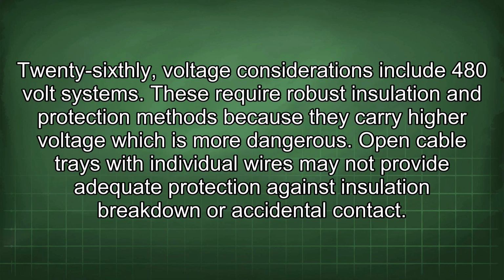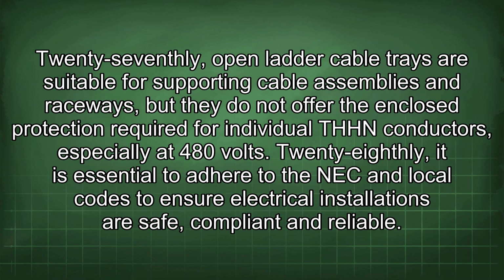26thly, voltage considerations include 480 volt systems. These require robust insulation and protection methods because they carry higher voltage, which is more dangerous. Open cable trays with individual wires may not provide adequate protection against insulation breakdown or accidental contact. 27thly, open ladder cable trays are suitable for supporting cable assemblies and raceways, but they do not offer the enclosed protection required for individual THHN conductors, especially at 480 volts.